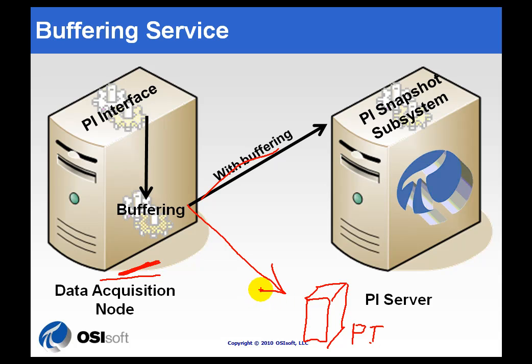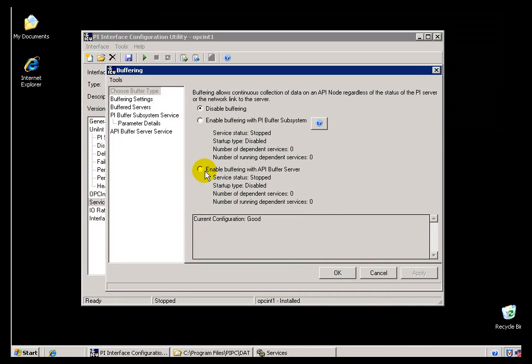It's not going to vary by much, but it's going to vary enough that we would strongly suggest you use the PI Buffer Subsystem. Another reason we recommend it: when you're using a Collective and you add a third PI Server to that Collective, the PI Buffer Subsystem will automatically be informed of that — something you don't have to configure manually. With the API Buffer Server for N-Way Buffering, you would have to configure that manually yourself.